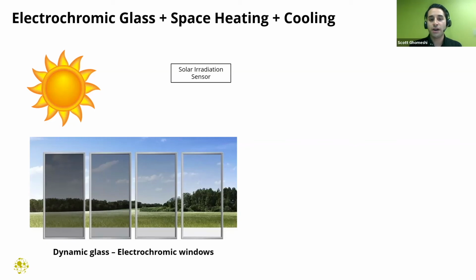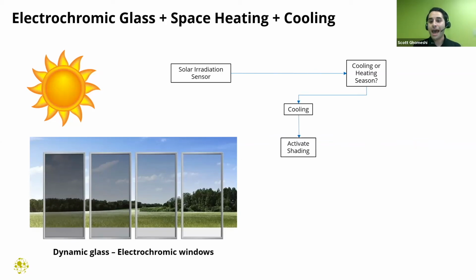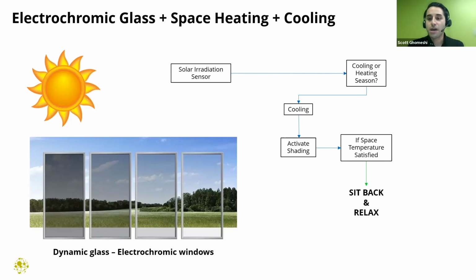But we layered that into the building automation system so we could harness the ability to turn the shading on and off based on the season. Depending on whether we're in heating or cooling season—say cooling season—we'd want to first activate the shading and wait, actively allowing the system to pause before activating any other system. If it's able to meet the space temperature or at least mitigate the gains so the space temperature is satisfied, we can sit back and relax.